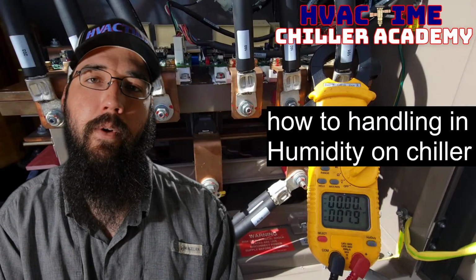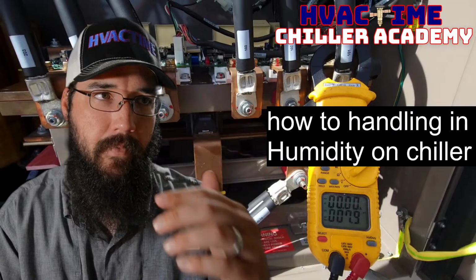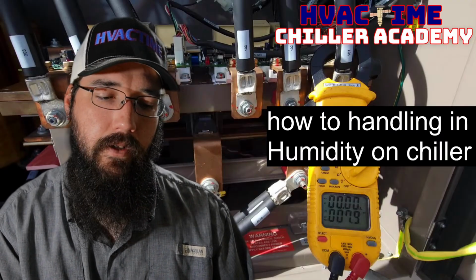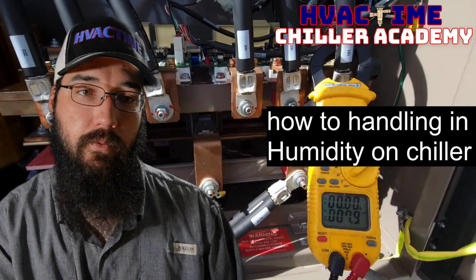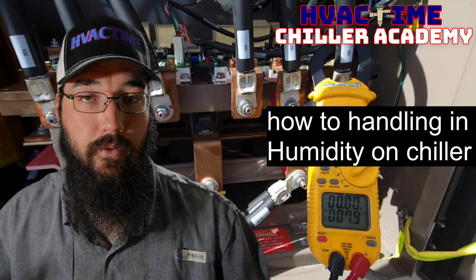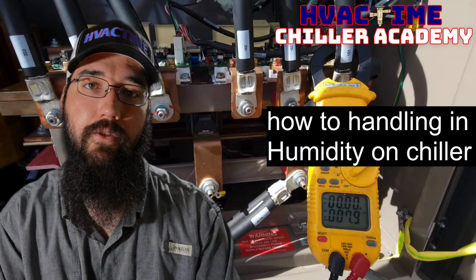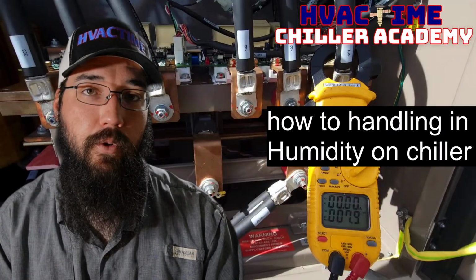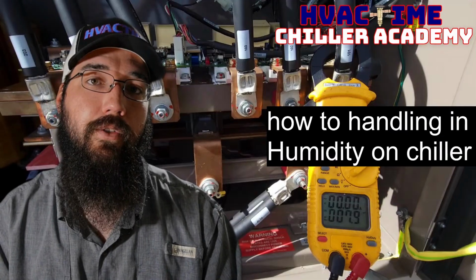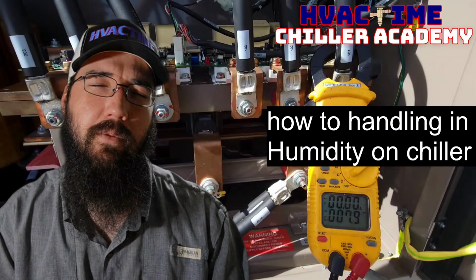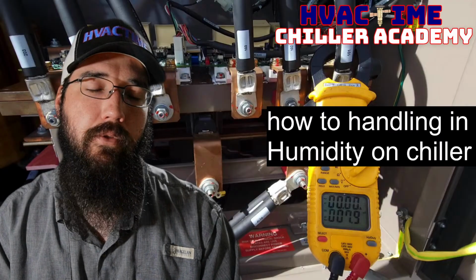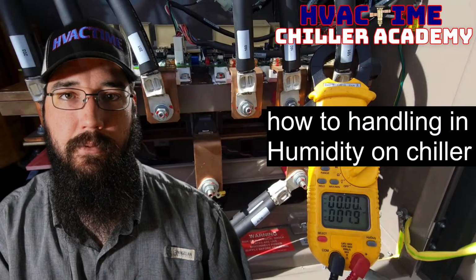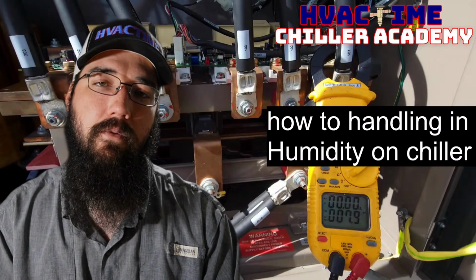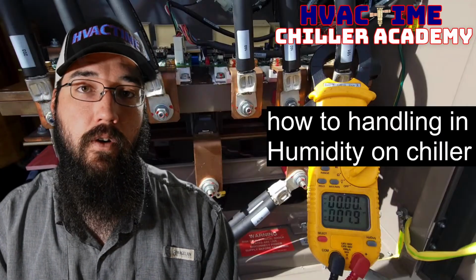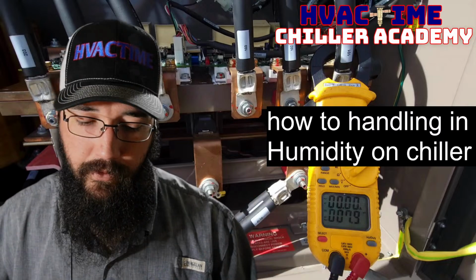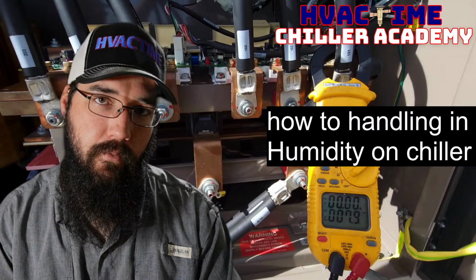If your median set point is 45 degrees on the chill water set point, but you're struggling to meet humidity requirements, whether it be a comfort cooling space or a data center, where you've got a server rack and very critical humidity control. And if you're not familiar, it is very common to use chill water coils in data centers. Many of these, especially smaller ones, I see are refrigerant based coils, DX based, right? We've got actual refrigerant in the coil. But a lot of your larger ones, in my experience, are going to be chill water based. You're going to have a whole bank of chillers and reserves. It's a whole thing, data center life. But anyway, humidity is critical.